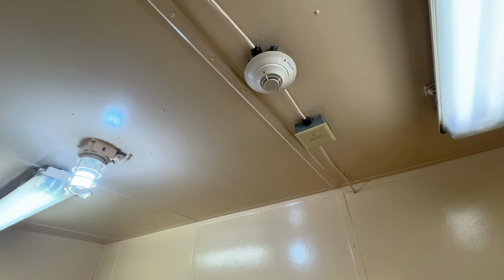While I have the video paused here, this is also a good time to take a look at this emergency fixture. You can see that light, which is installed on the left of the screen with an E in it. From my past experience on ships, that usually means it's an emergency light.